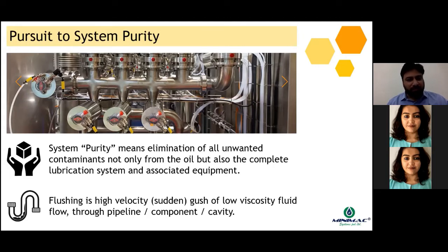So what is flushing? Flushing is a high velocity, sudden gush of velocity. A sudden gush is very important out here. So sudden gush of low viscosity fluid through the pipelines, through the components, or through cavities. So with this definition, we can understand that flushing doesn't just happen for pipelines. Flushing happens for the entire system, and the cavities, the components, pipeline internals, everything is a part of the system. So flushing with high velocity, that's for the entire system and not just the pipeline or the piping.